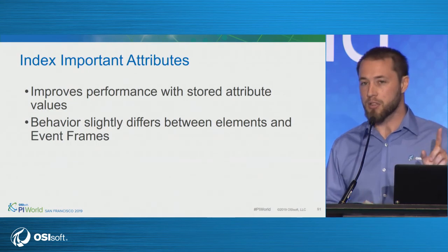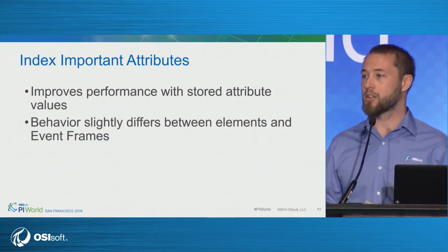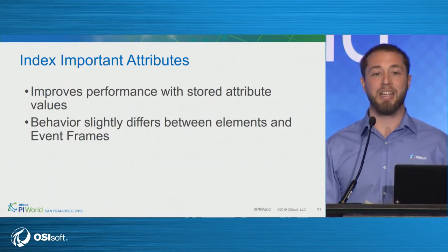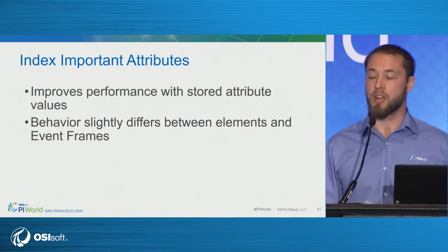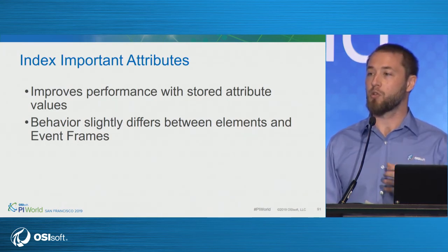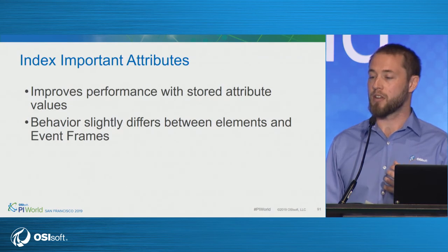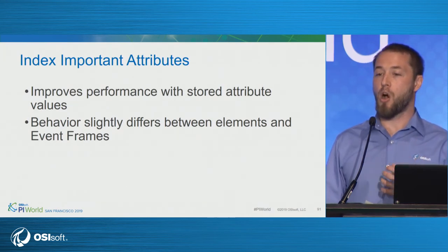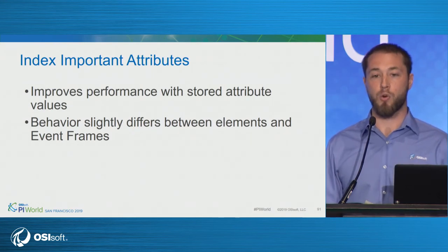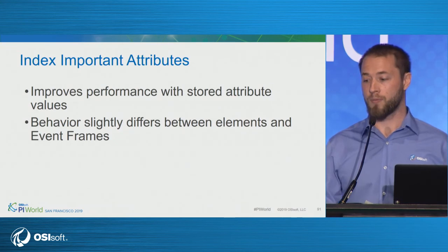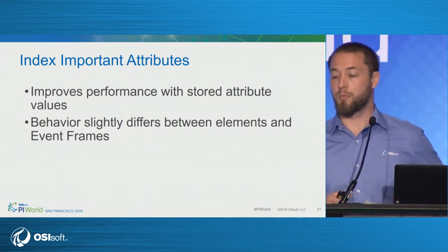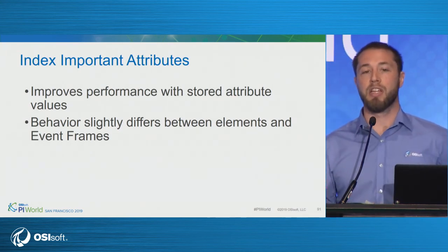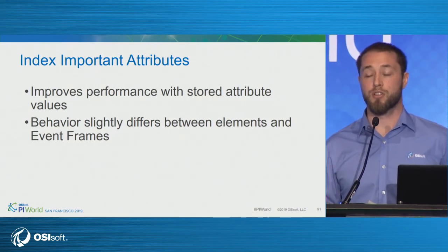There is a small subtle difference between indexing attributes on elements and indexing attributes on event frames. Indexing attributes on elements doesn't really provide the same benefit as event frame attributes because not all element attributes are actually stored on the SQL server. All event frame attributes, though, are. So that's why indexing important attributes for event frames can really yield faster searches and better search results.